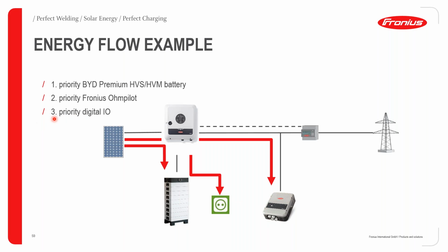And if we still have even more excess energy after hot water has been generated, because what I should mention here is that the Fronius Ohmpilot is also connected with a PT1000 temperature sensor. And once you have achieved your temperature, the Fronius Ohmpilot is not going to be consuming any more excess energy. And therefore, that priority can also be set using the digital IOs. As I mentioned before, we can have some very dedicated sessions where we look at the very specific application features of the different inverters. So the digital IOs is something that we can cover in a separate training for the Gen 24 and also for the SnapINverter series.